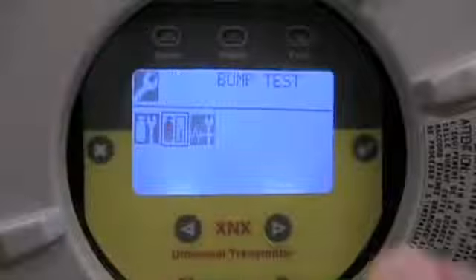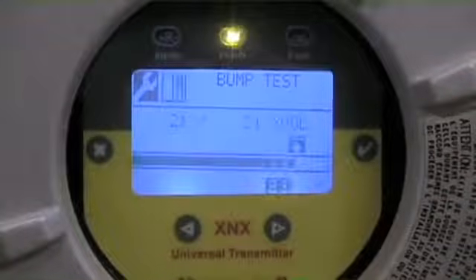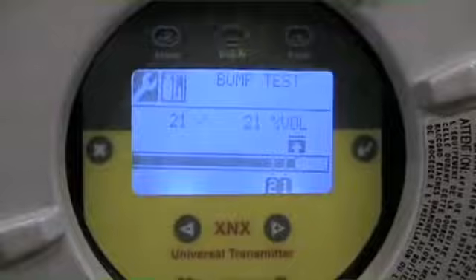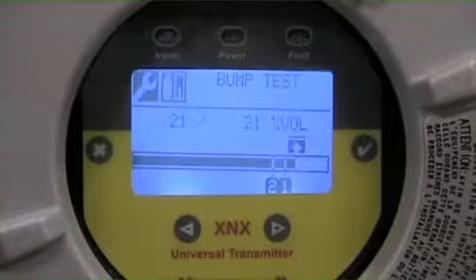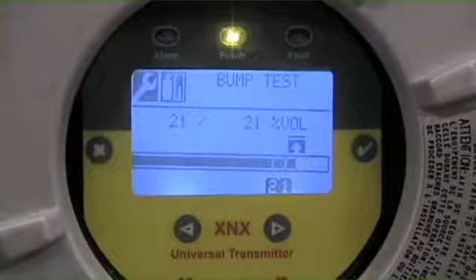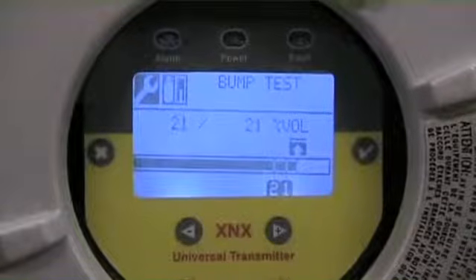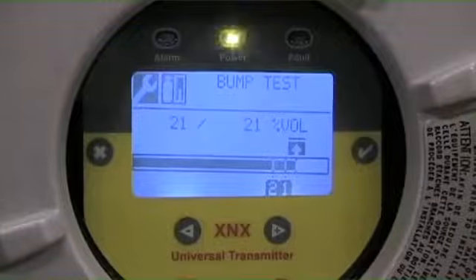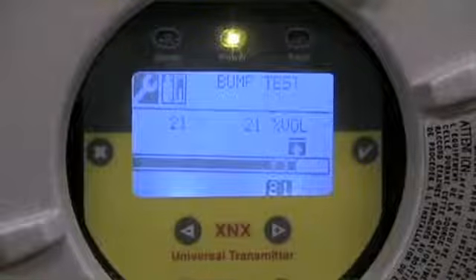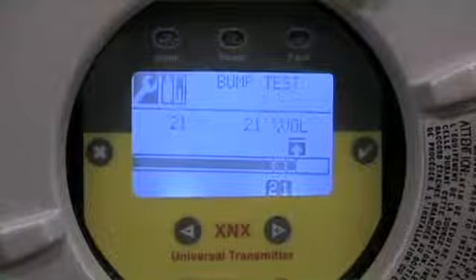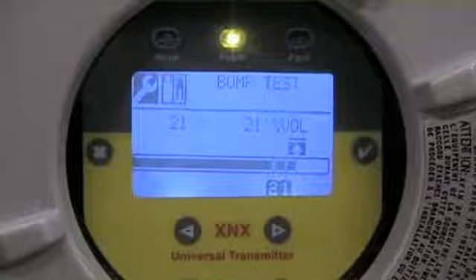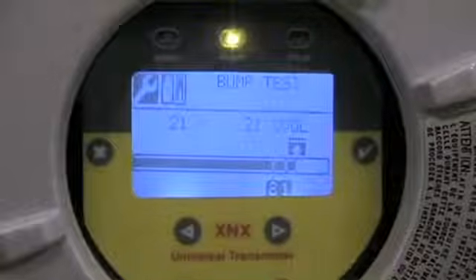And again, we'd enter into this menu, we'd arrow over accepting it, and then in this menu we end up in a current concentration range. We'd end up putting on a known concentration, 15%, whatever number in the case of oxygen, or 50 ppm of CO. You'd have your challenge gas, and you'd apply it, and you'd make sure that you're reading within that target gas range. So that's a bump check. It's a quick field verification. Doesn't change any of the sensor set points or setup functions. It's just a way to make sure the sensor is reading what you want it to read.